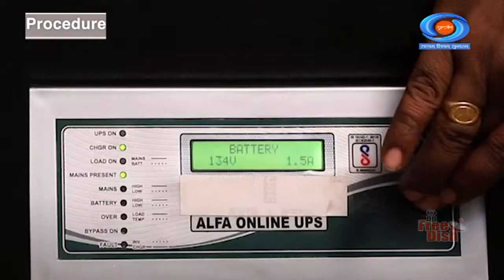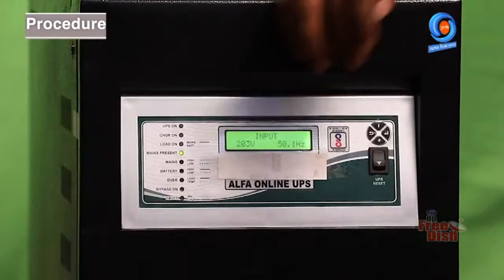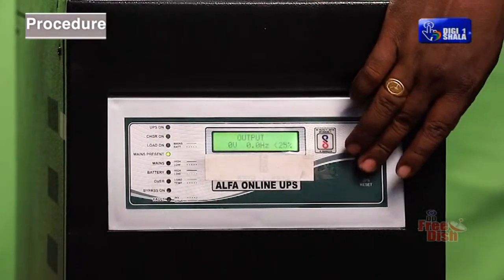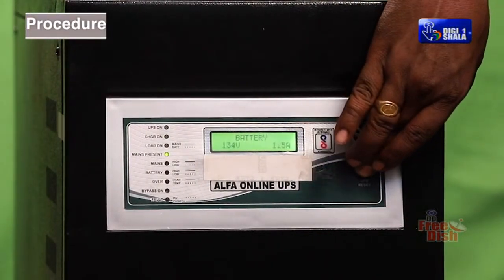Press the on-off test silence button for less than 1 second in backup mode. Observe the audible alarm; it should be silenced. It does not function under low battery or overload conditions. Check the beeping alarm when pressing the silence button.